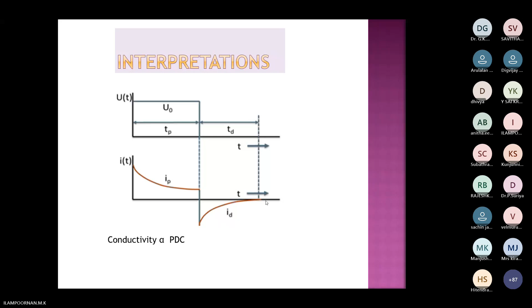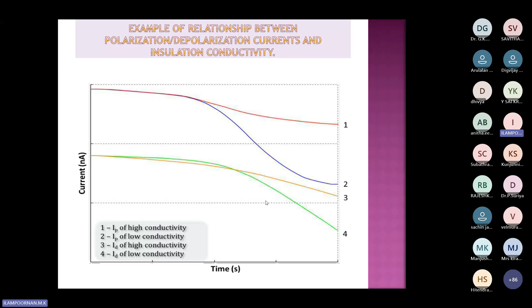Inversely proportional, sir. Resistance is inversely proportional to conductivity. Current is directly proportional to the conductivity. The higher the conductivity, the more the current. As the conductivity increases, what will happen? The current will be flowing more. That means you are quickly charging and discharging. That means your insulation is bad. Okay, so that's the idea behind it.